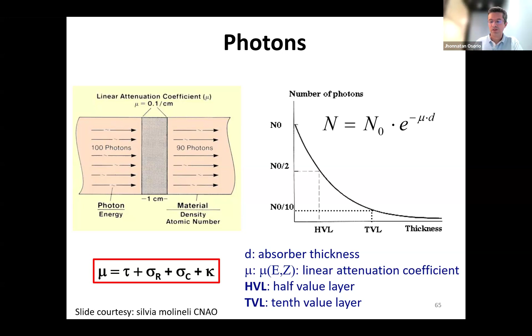So basically the source of the calibration that you make in your images, that is the Hounsfield units, is based on the linear attenuation coefficient, which is basically the physics of the interaction of your photon beam inside the patient, which makes it simple, let's say, to provide this really key information, that is the geometry of the patient. In the case of particle therapy, this doesn't work anymore because we don't have a linear attenuation coefficient.